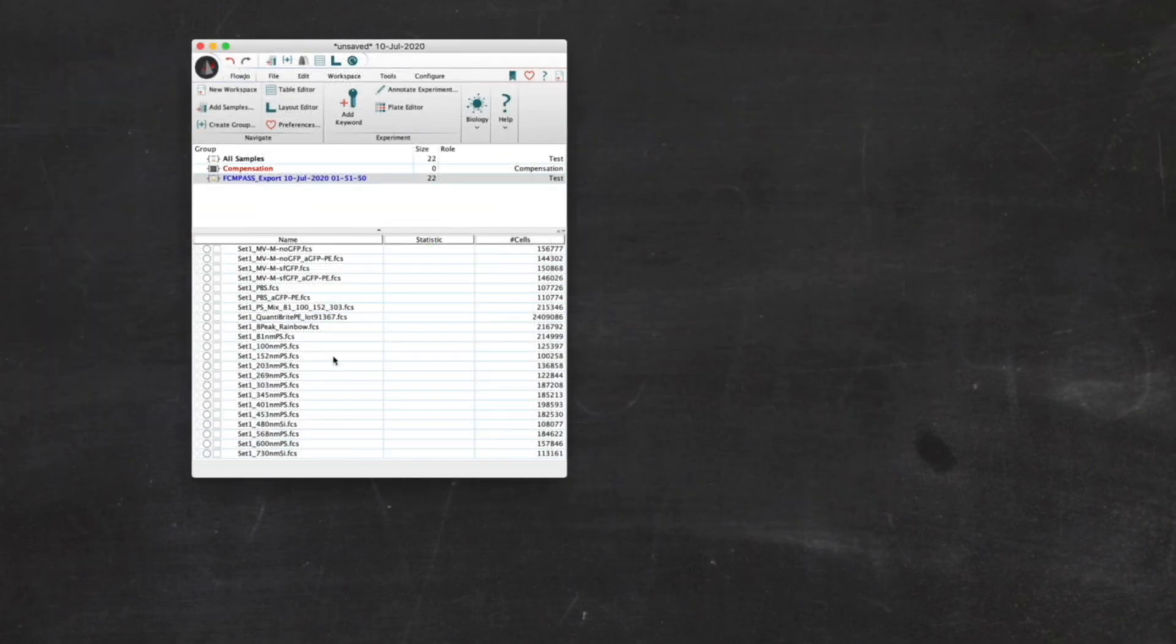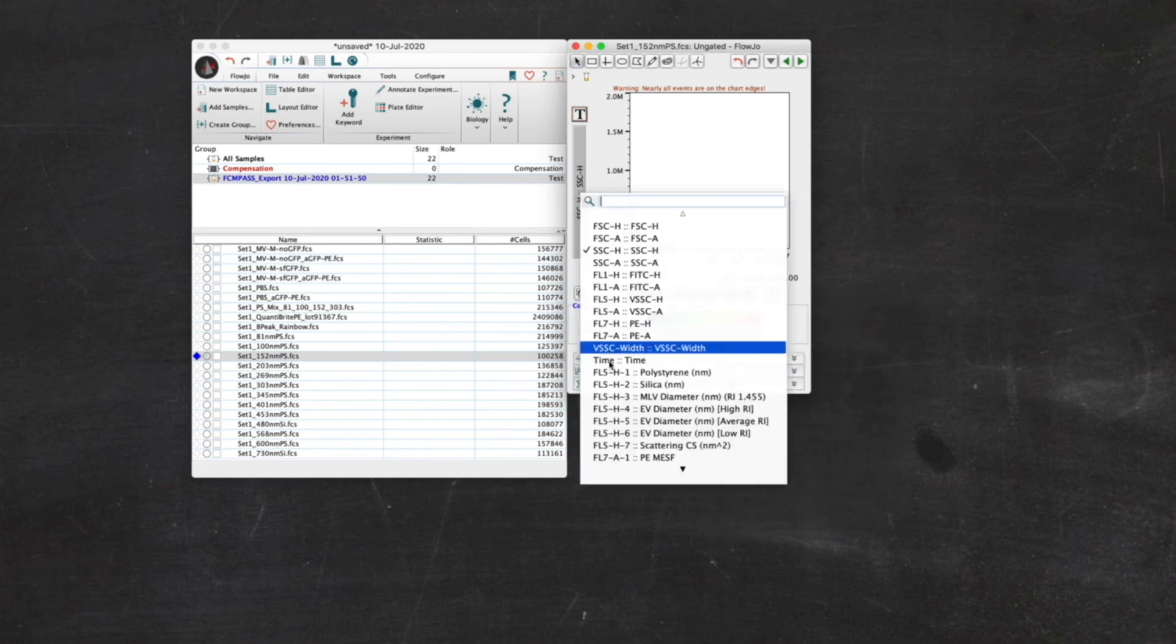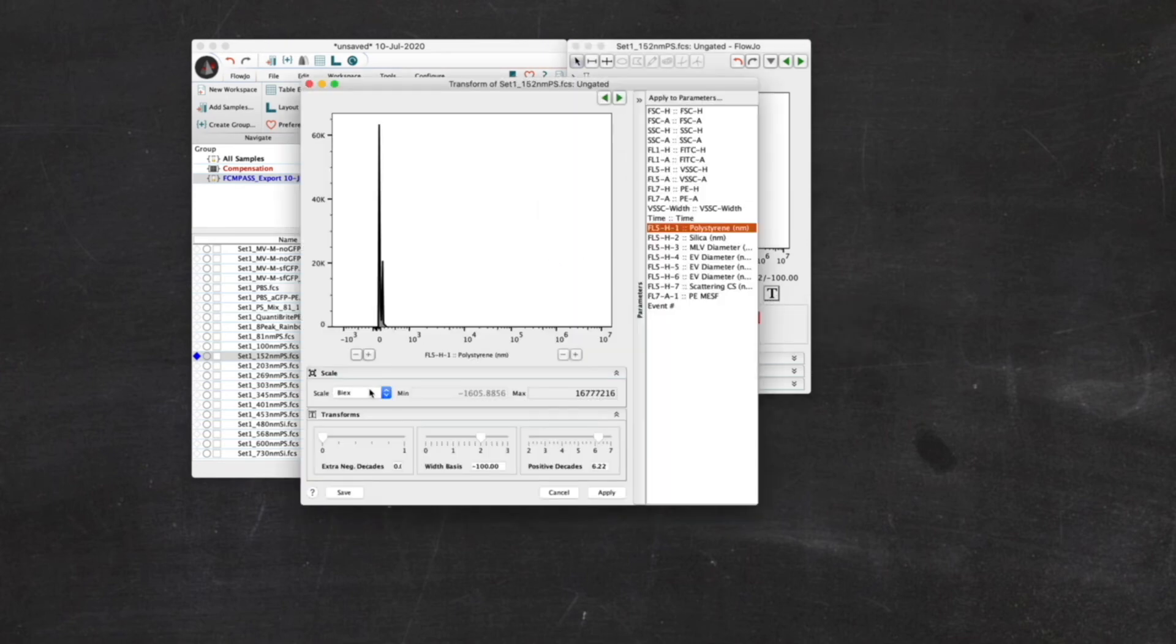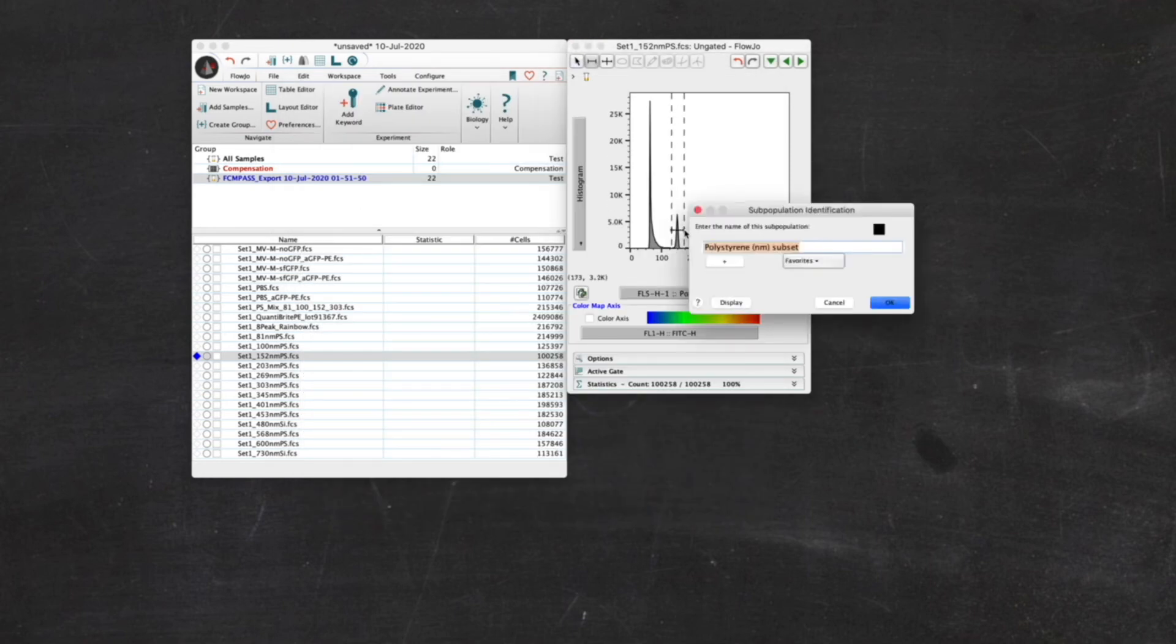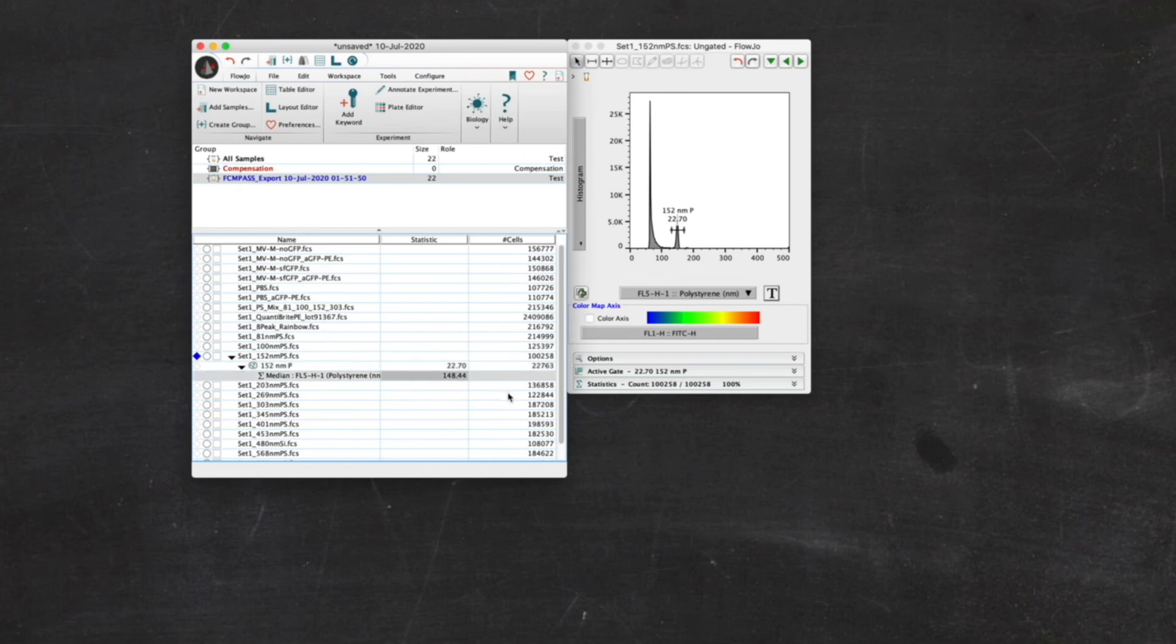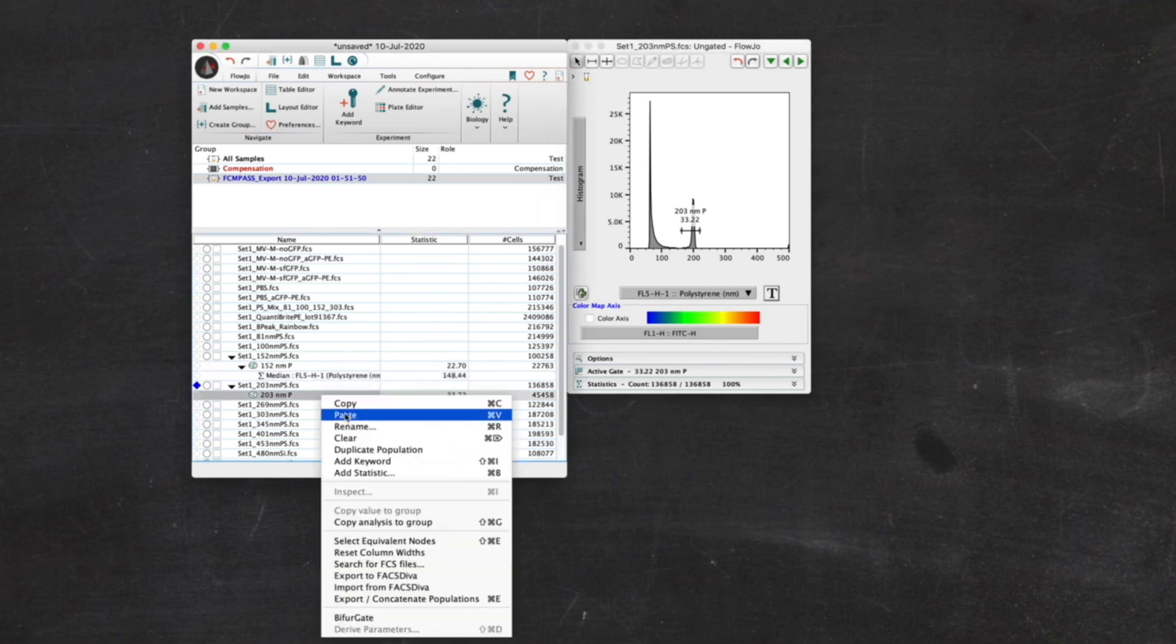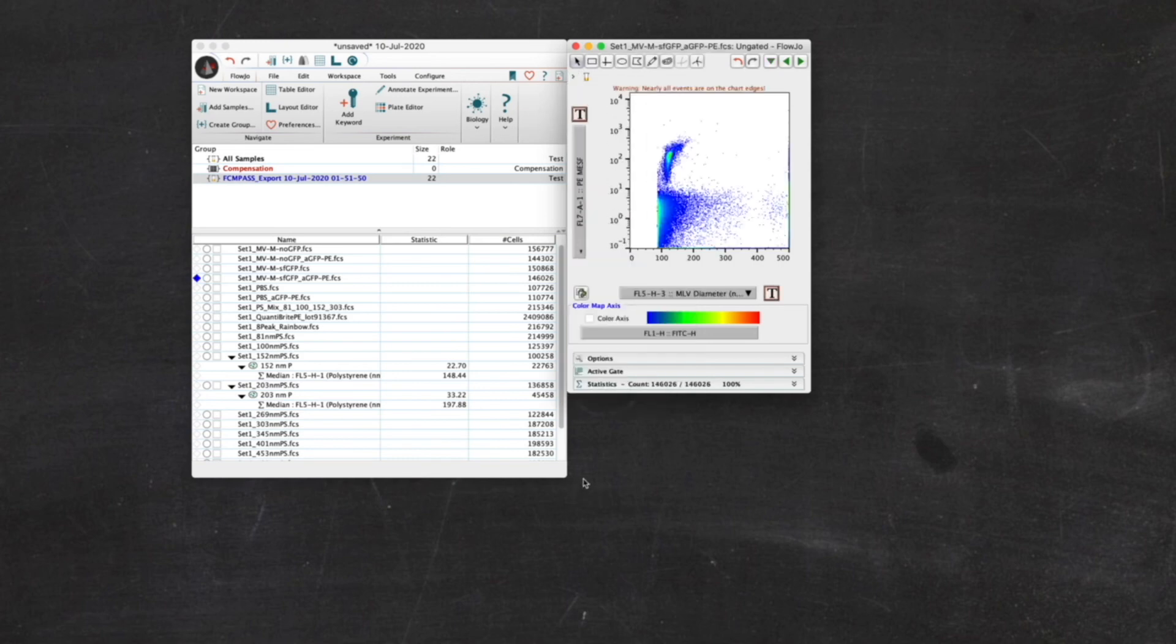Now just looking at the calibrated files, you can see when we go to the drop down with all the parameters, all of the standard parameters are at the bottom. And on the left, you can see that the parameter that they were originally converted from. Something that I wanted to show you is that many of the scales might need changing. The diameters, for example, we want to go to a linear scale. And ideally, we want to look at the smaller range. Everything we're kind of interested in with this murine leukemia virus is down in the kind of 150 region. So if we put the scale to 500 nanometers, it should be sufficient. And you can see here, if I just gate around the 152 nanometer beads and the 203 nanometer beads, and get the median statistic for polystyrene, we come out at 148 and 197. So we're four or five nanometers out, but we're very close. And this is how the data was generated in the paper that was published. So you can see PE-MESF versus murine leukemia virus diameter here.